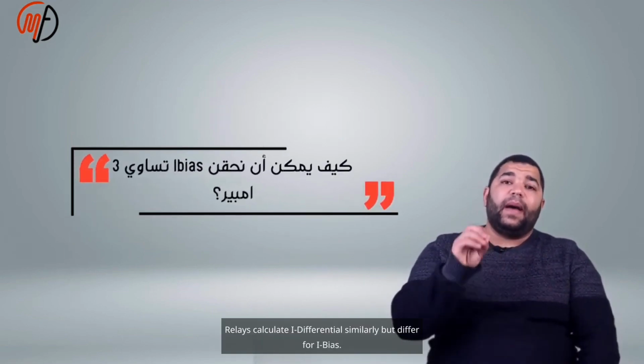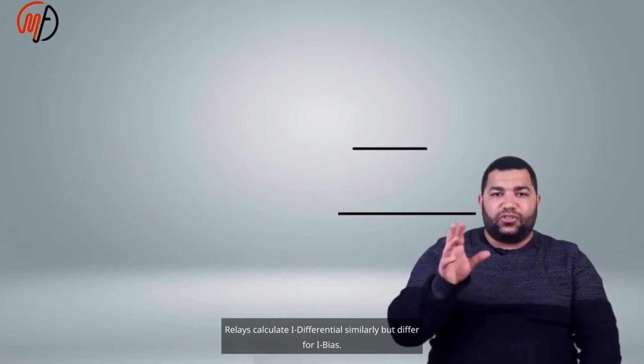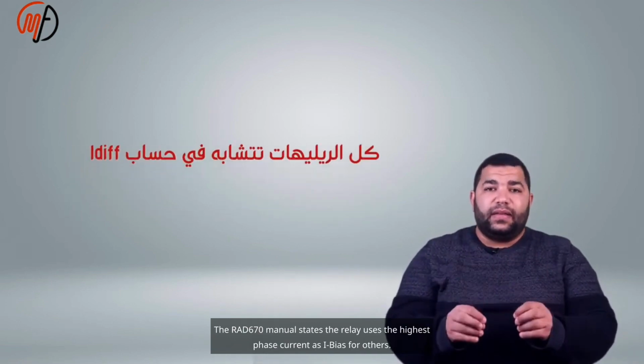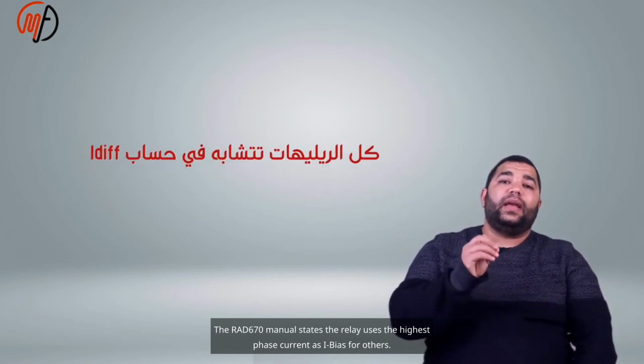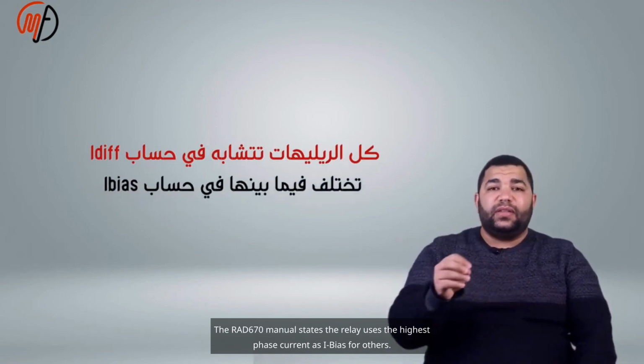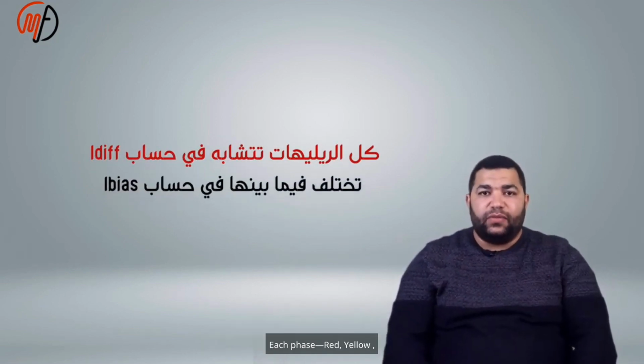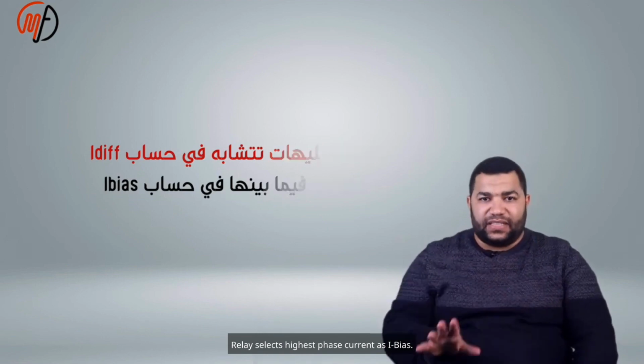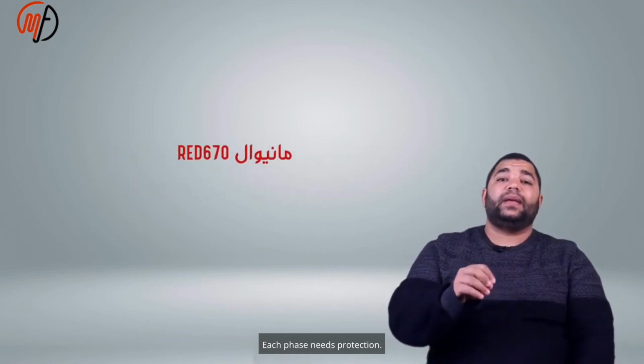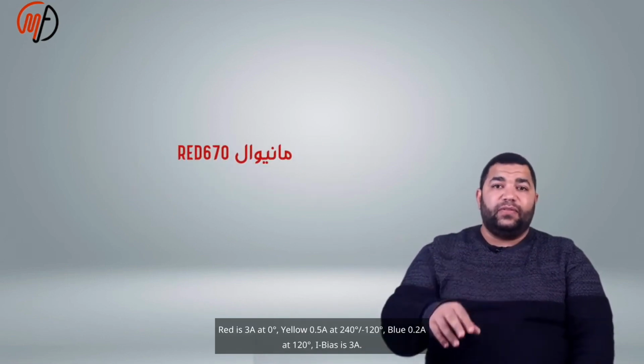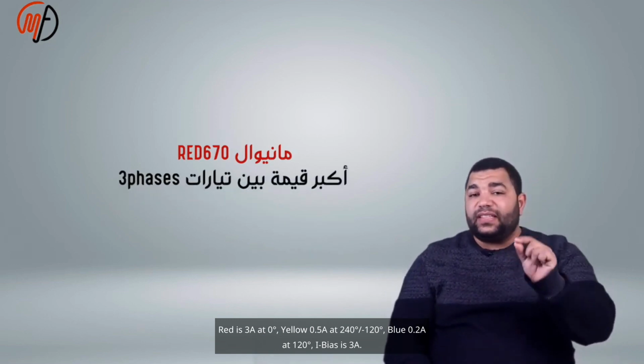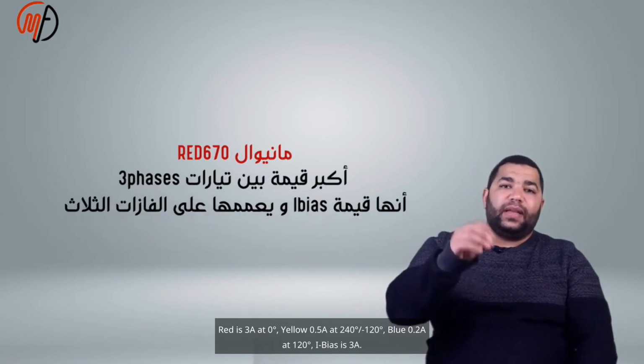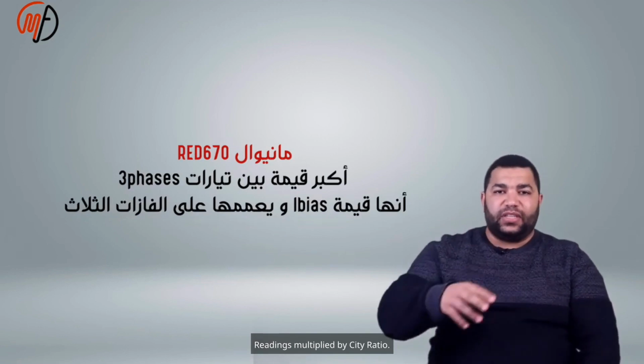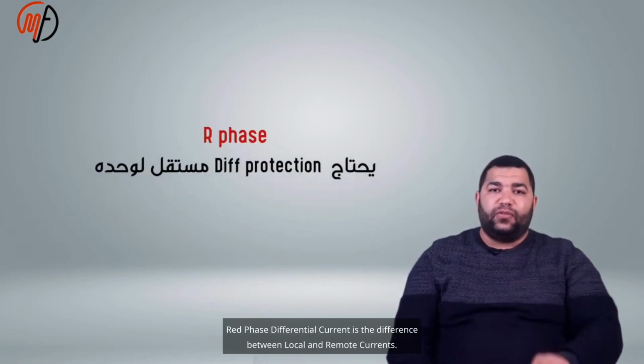An engineer might ask how to inject 3 amperes I bias. Relays calculate I differential similarly, but differ for I bias. The RED670 manual states the relay selects the highest phase current as I bias for each phase, red, yellow, and blue. Each phase needs protection. Red is 3A at 0 degree, yellow 0.5A at 240 degree, blue 0.2A at 120 degree, so I bias is 3A. Readings are multiplied by the CT ratio. With 800:1, I bias is 2400 for all phases.